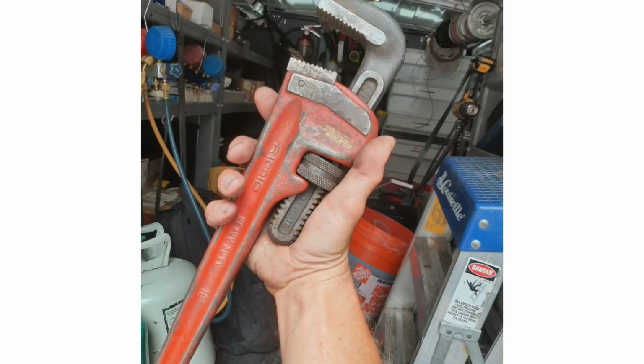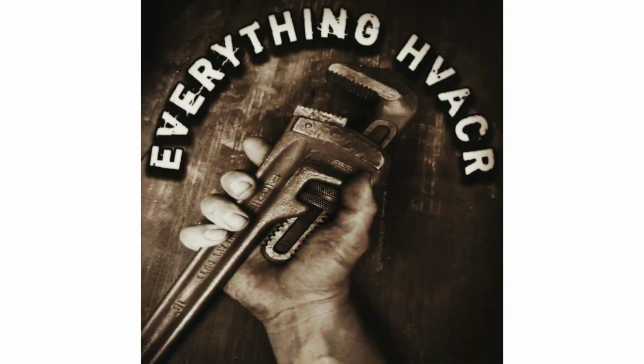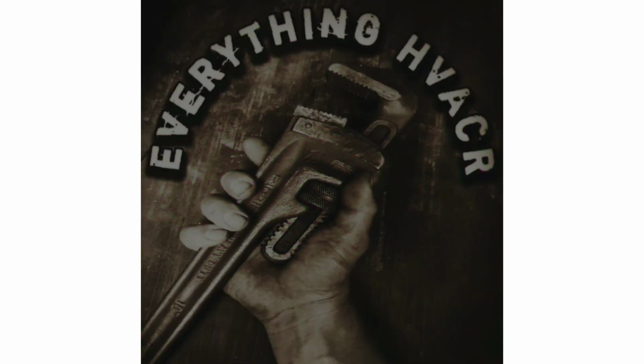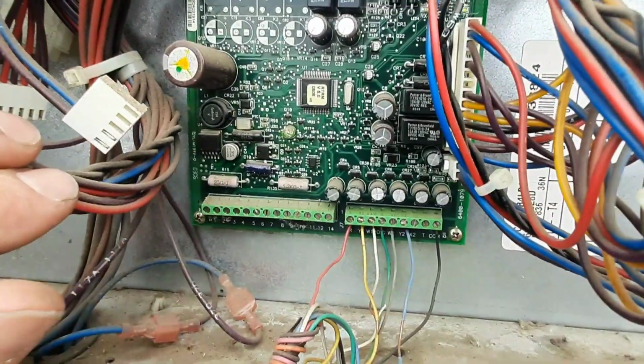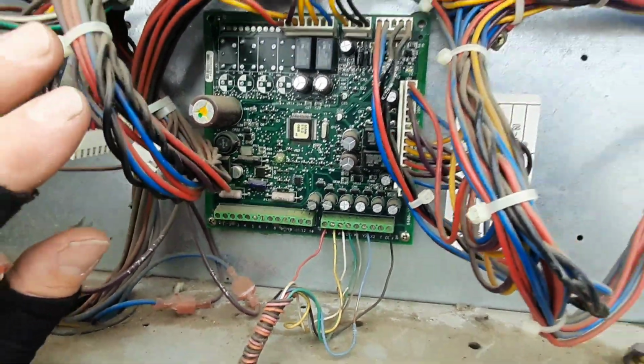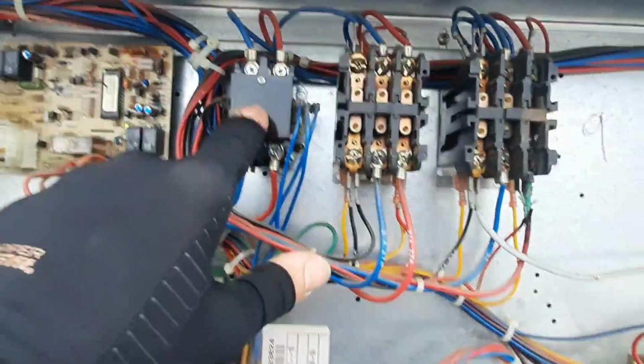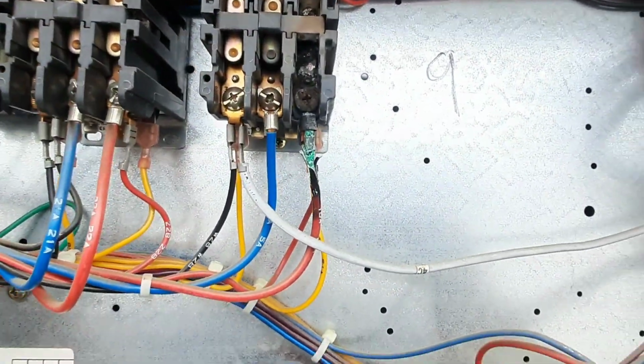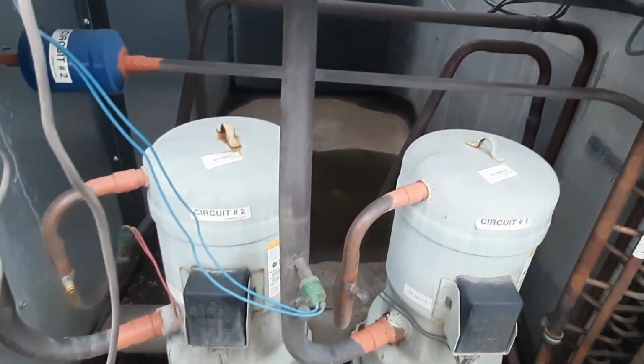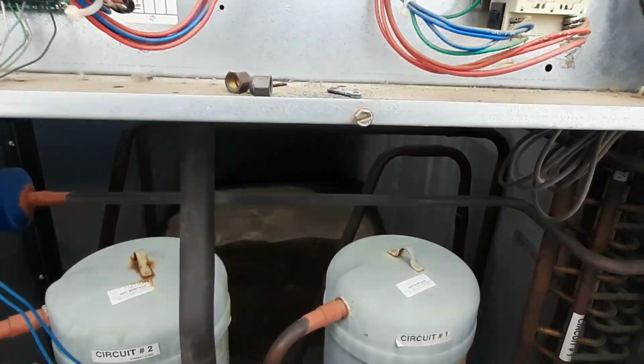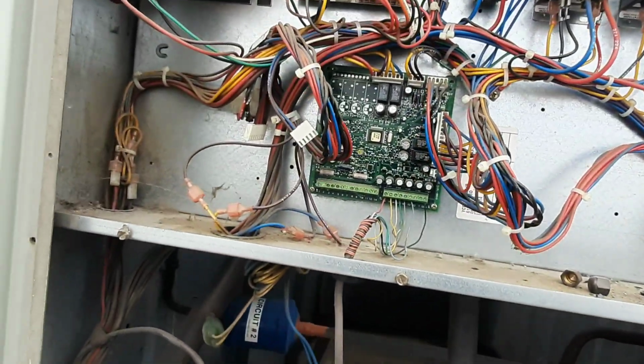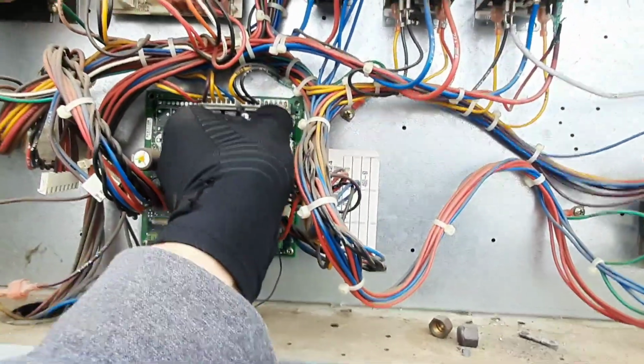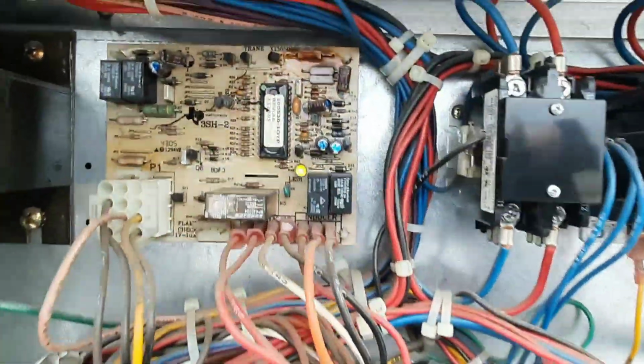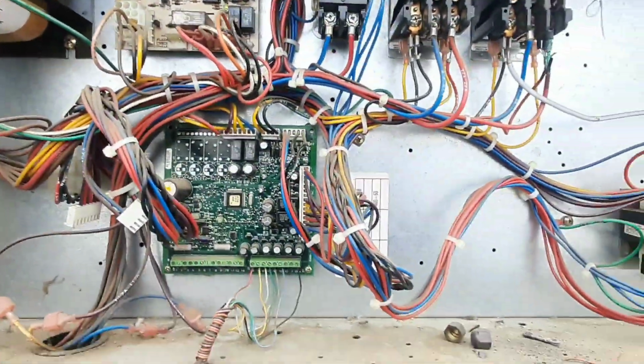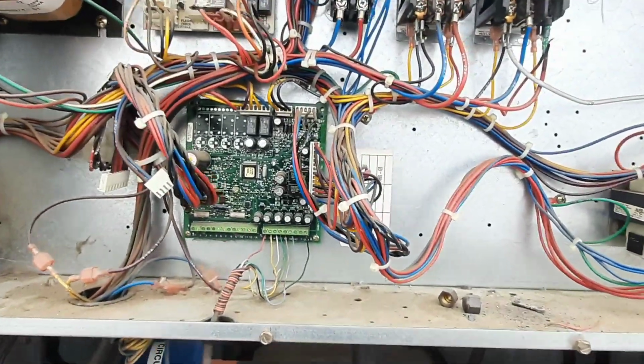So let's pop our panel off, see what's inside. So I do have some kind of flash code on my RTRM. There's my blower contactor. That looks nice. Looks like both compressors are still connected. So that could be a problem. Why my blower signal should come, it's got to come from RTRM. Look at that heating board. These are old units. So let's get a meter out and get in here and see.